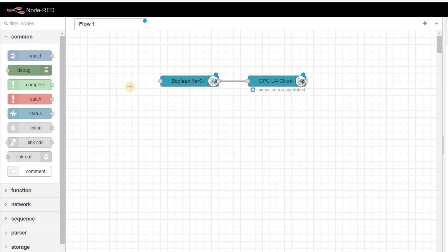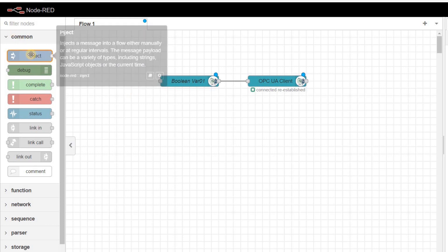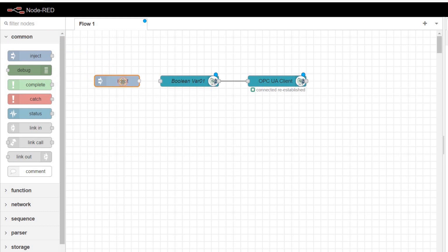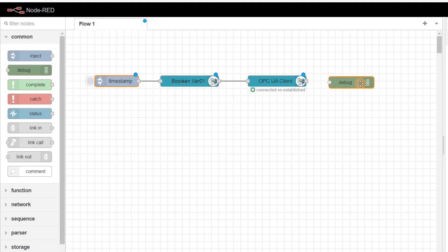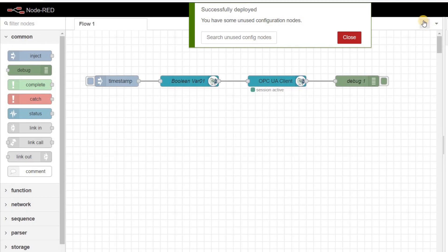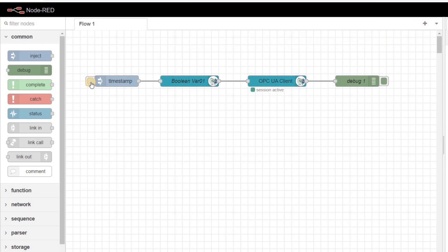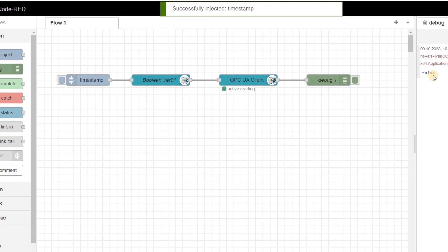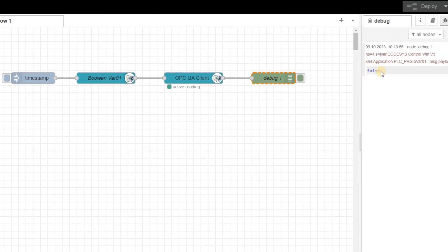The next step is to determine how often we want to read the value. For that, we need an inject node in the flow and connect it to the OPC UA item. By default, in the run mode, we can click on the left side of the inject node and initiate the reading process. We also need a debug node to show the value of the variable that we read. We are ready now to deploy our flow and run it. Each time that I click on the left side of the inject node, we read the value of the boolean variable.